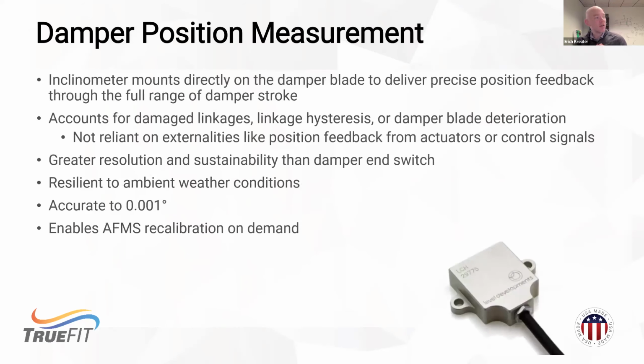So, a little bit more on the inclinometer. This is mounted potentially in the outdoor airstream. It's a hermetically sealed, highly accurate device. There's no maintenance related to it. Unlike other measurement technologies that put pitot tubes or thermal dispersion sensors in the dirty air, there's nothing here that can get contaminated or need any ongoing maintenance.